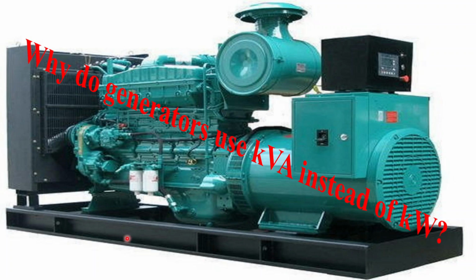The relationship between these types of power is given by the equation: kVA is equal to kW divided by the power factor. Since the power factor can vary with different loads and conditions, the generators must be rated to supply the total apparent power, kVA, regardless of the power factor.